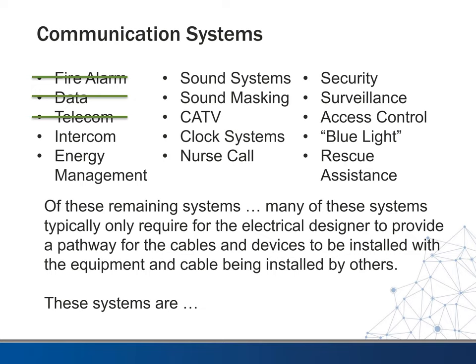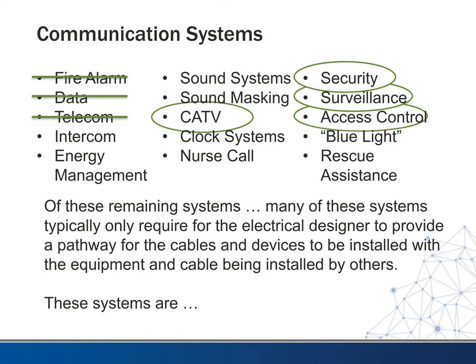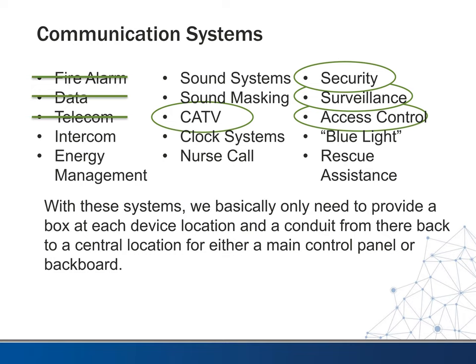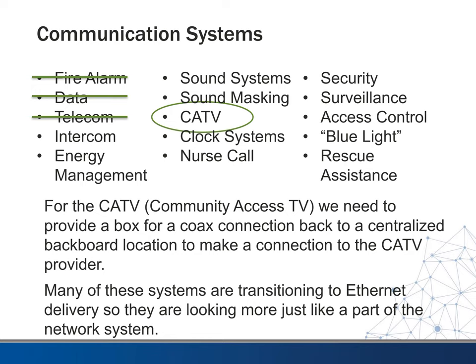Systems in this category include cable TV, security, surveillance, and access control. For these systems we basically only need to provide a box at each device location and a conduit from there back to a central location — either a main control panel or a backboard. For community access TV, we provide a box for coax connection back to the centralized location so they can make a connection to the CATV provider. Many of these systems are transitioning to Ethernet delivery, so they're looking more and more like another part of the network system and they integrate with it in many cases.